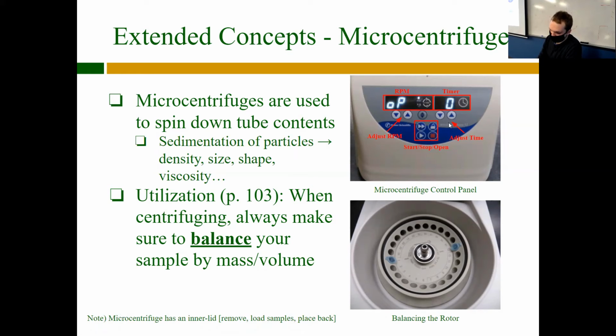Here is the timer. Same thing, adjust time there. This is pretty straightforward. The start button, the stop button, and then the lid opener. So this thing's not going to open when it's spinning because it poses a danger to you, and it could also break the device. So you have to wait till the timer is done, and you can press or click stop. Then you can press the open button, and the lid will unsecure.